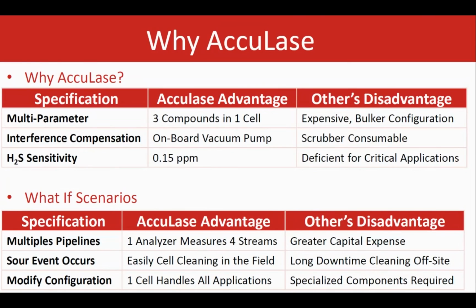Using the vacuum pump, as I mentioned earlier, enables a more accurate measurement with a lower LDL, in combination with the Herriott cell as well as the WMS. With these measurements, you need not worry about any background interferences or matrix effects. It's really immune to those. The measurement is direct and therefore doesn't require consumables, scrubbers, or any other sources of indirect measurement.